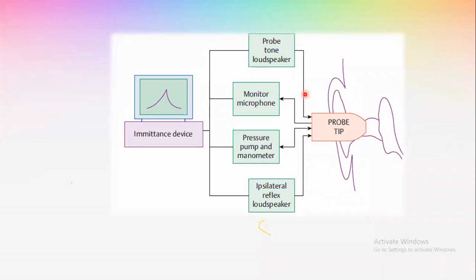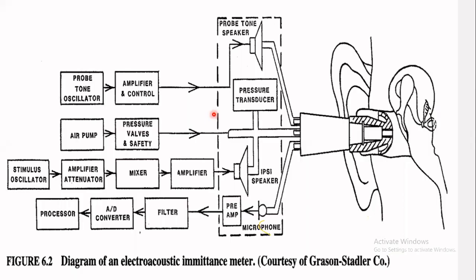In detail, the probe tone is generated by an oscillator, then amplified and delivered through the probe tip. The air pump or pressure transducer provides various pressures. A third speaker provides the ipsilateral stimulus for reflex measurement. Whatever bounces back from the ear canal is measured by the microphone and analyzed by the processor.